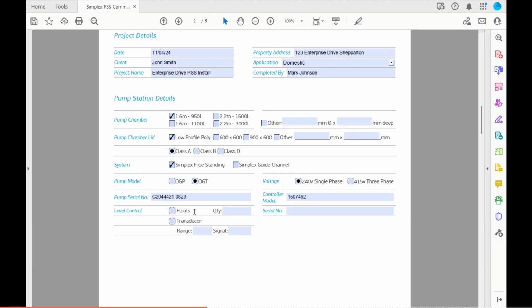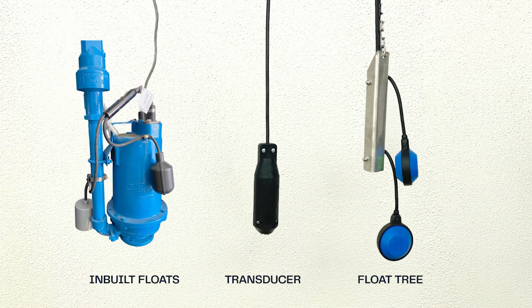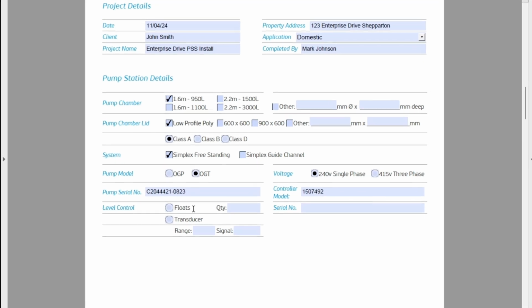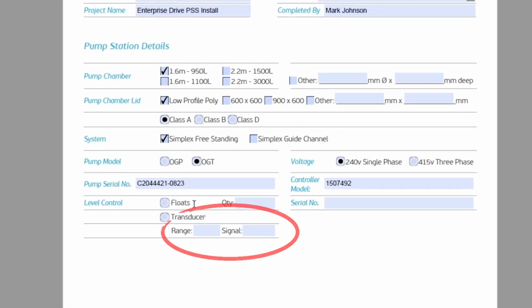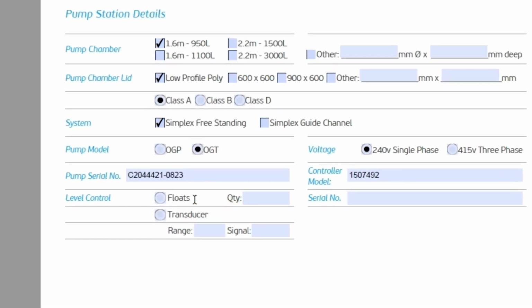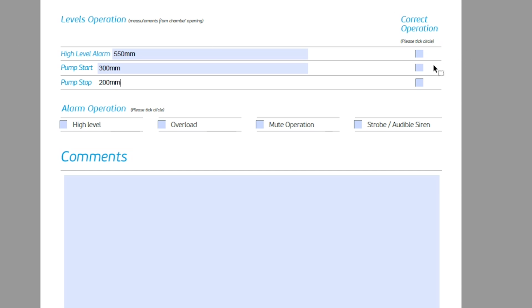Specify what level control is installed. This would typically comprise of level control type and range. In the case of a level transducer, you also need to capture the signal type in terms of level control range. It could be a 0 to 3 meter range or a 0 to 10 meter range as an example. Ensure all of this is recorded on the final report.